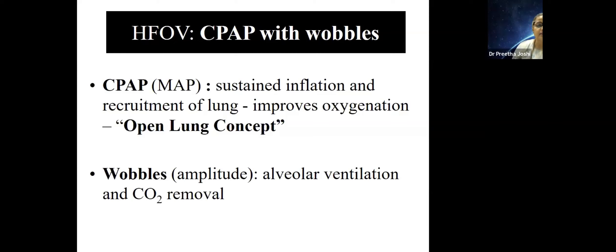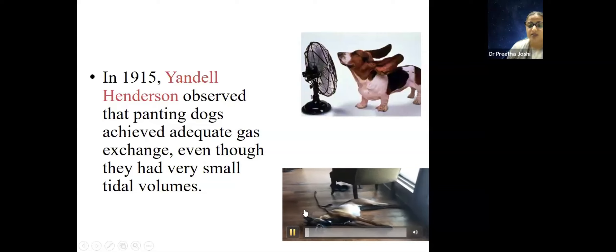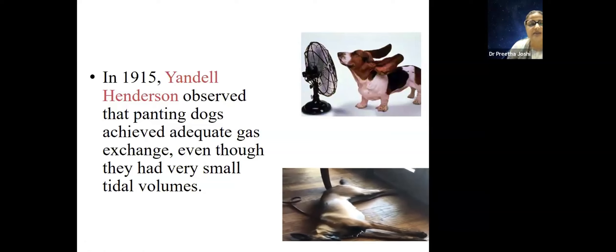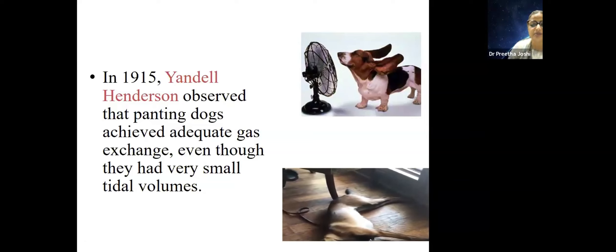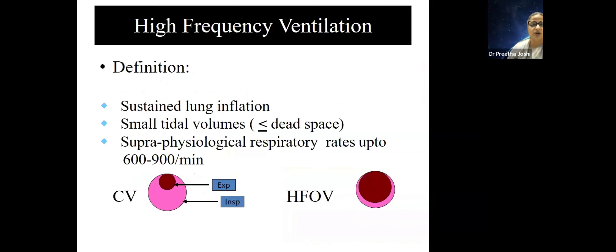This idea started with an anesthetist who was observing panting dogs. He found the dog breathing very fast after a run but still able to ventilate itself without becoming blue — so there is adequate gas exchange even through very small tidal volumes. High-frequency ventilation is a sustained lung inflation giving very small tidal volumes, less than dead space, at supraphysiological respiratory rates of up to 600–900 per minute.